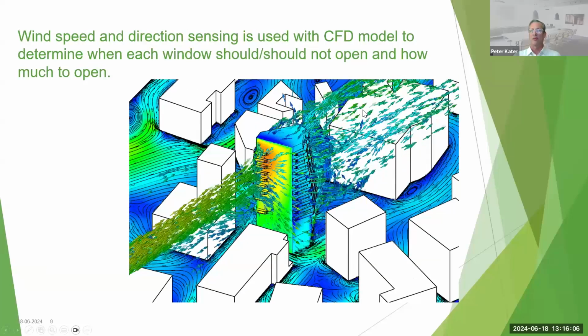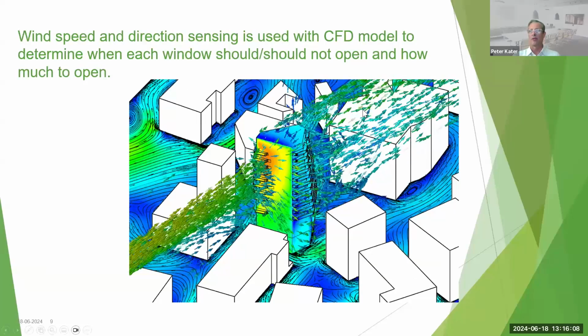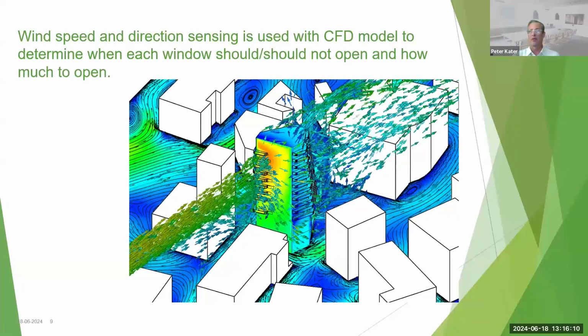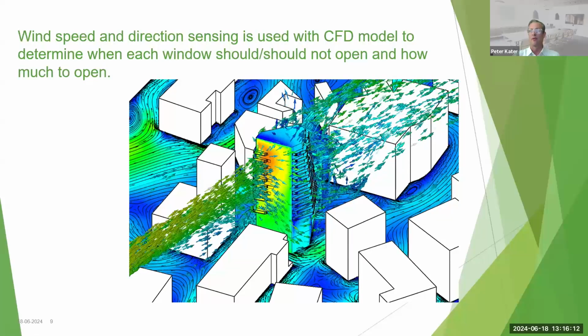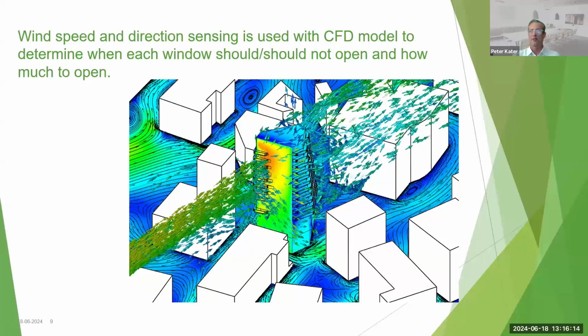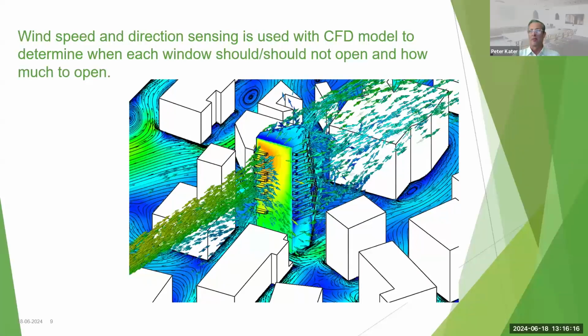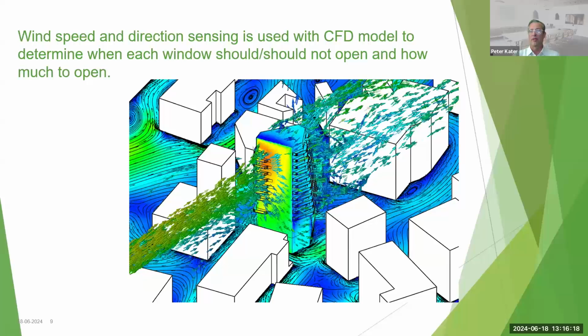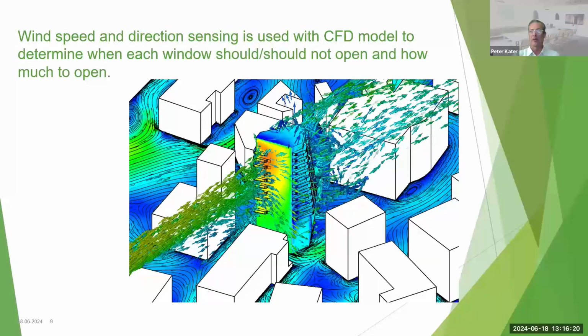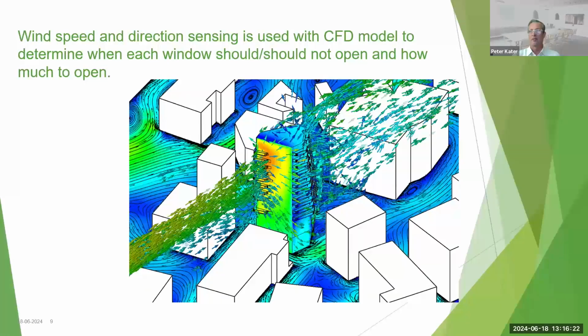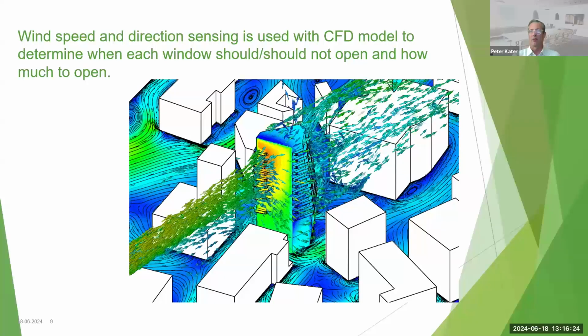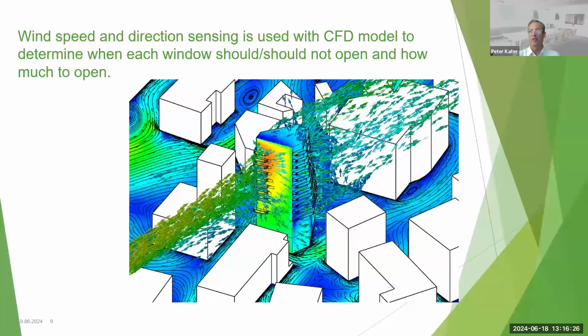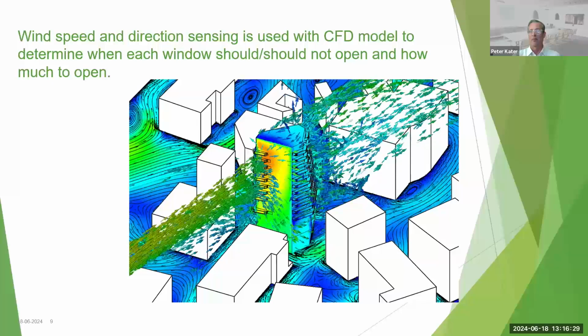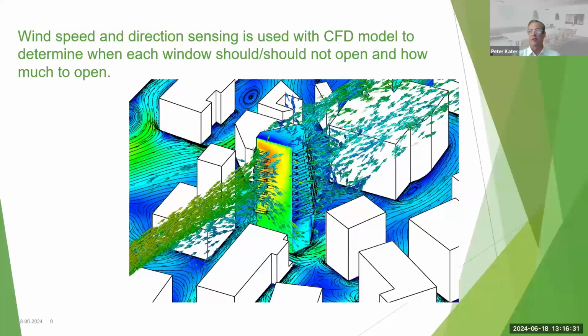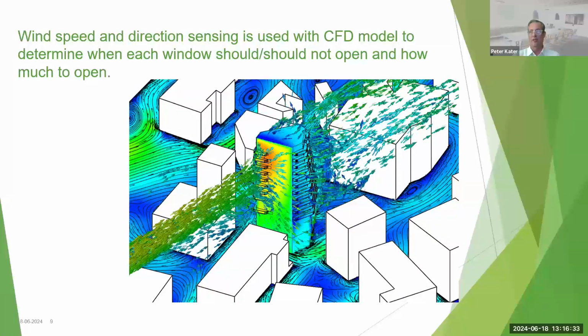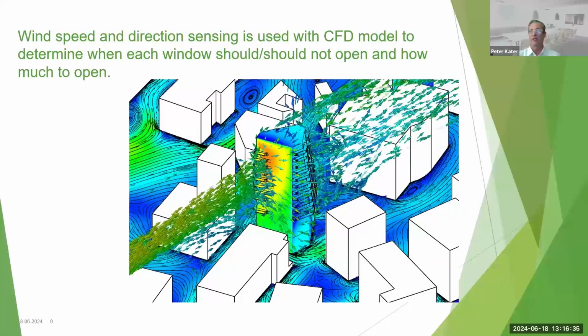Typically what we'll do during the design phase for a new building, or even for refurbishments as well, is a CFD analysis. We'll simulate the wind speed and direction around all the points of the compass and determine what the wind pressure would be, positive or negative, and how much pressure there is at each opening or operable window location for a given wind speed and direction.